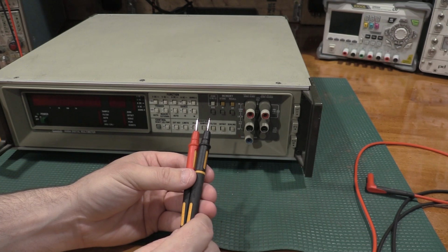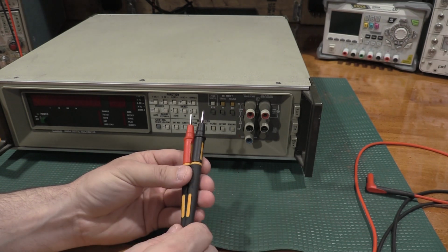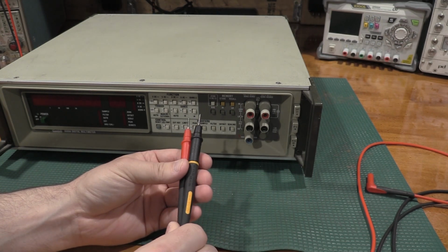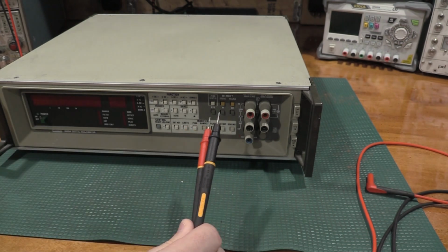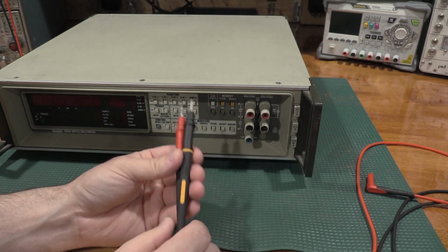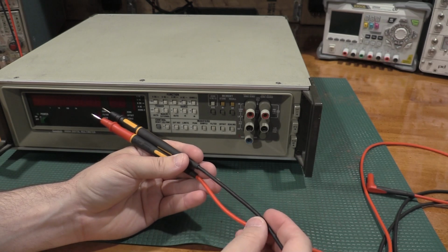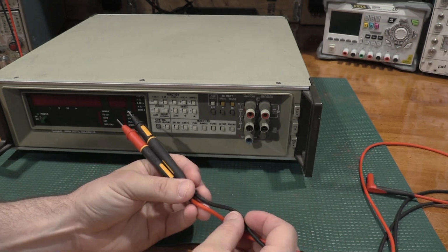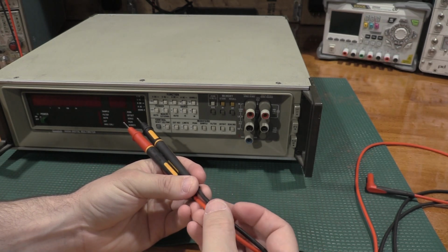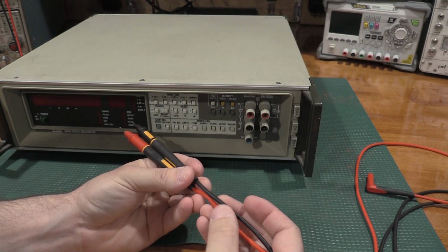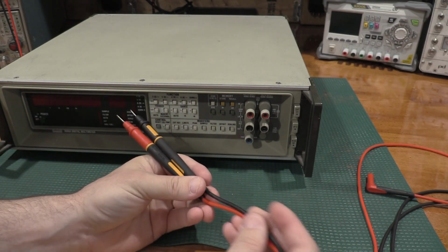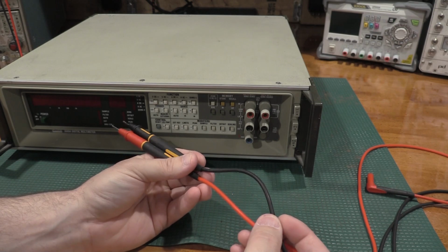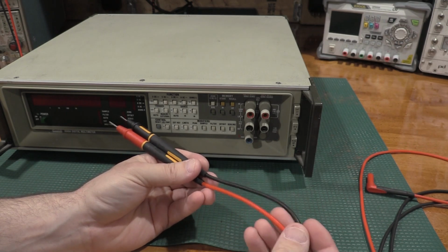So when I'm working on the industrial power stuff, I'm kind of picky about what my probes are and what my meters are because I don't want something blowing up in my hand. But these have a couple of safety features in there, like you check the leads, these are fine. They have a white insulation jacket underneath the red and the black, so if any white starts showing through, the leads have been damaged and they've lost some of their withstanding resistance and need to be discarded and replaced.